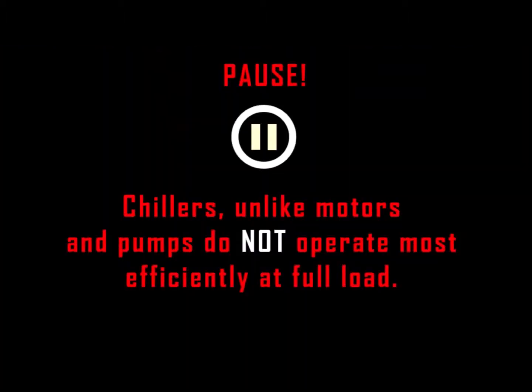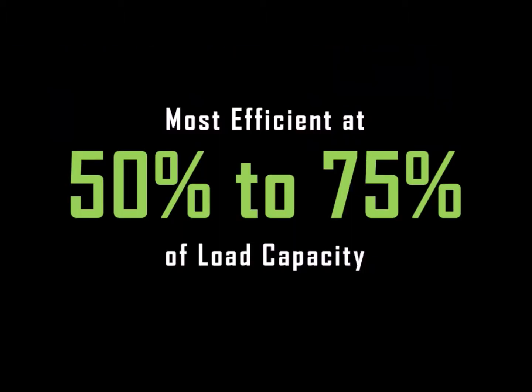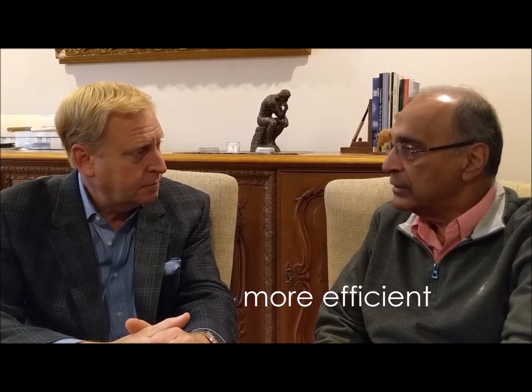But the most important thing to understand here is that chillers, the chiller compressors, unlike motors and pumps, do not operate most efficiently at full load. If you have a motor, its maximum efficiency is when it's running at 100% load, even 101, 102% of the load. Similar with pumps. But with chillers, the efficiency curves are quite different. They do not operate most efficiently at maximum loads. They operate most efficiently at somewhere between, say, 50 to 75% of the load. So part loading the chiller makes it more efficient.